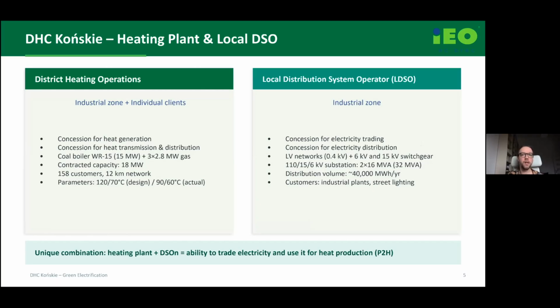That is also why the idea of power-to-heat technology is quite natural in this setup. One thing I should mention is that the system was designed for higher temperatures, above 100 Celsius degrees, but it operates at lower temperatures, mostly between 70 and 90 degrees on the supply stream of the network. This is important when we talk about heat pumps, because we need to reach these 70-75 Celsius degrees, so this is one of the problems.